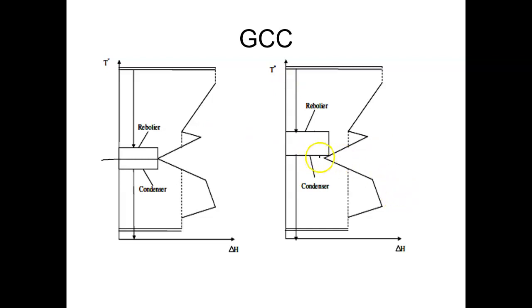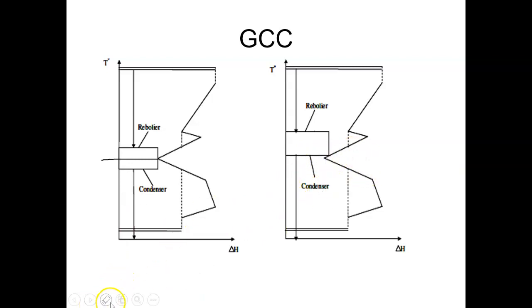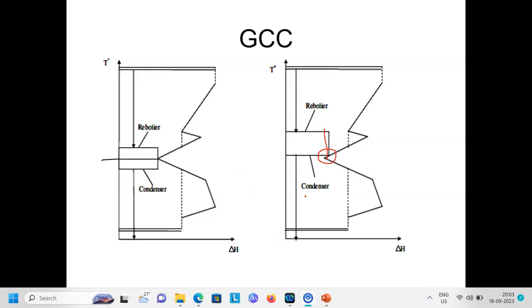Looking at the temperature values, it may seem like there is a good opportunity to integrate the column with the process. However, the overlapping between the available heat and the required amount is very small compared to the actual requirement. The only area where energy can be exchanged between the process and the condenser is limited, meaning only a small amount of energy can actually be saved. The rest must go to utility below the pinch point.